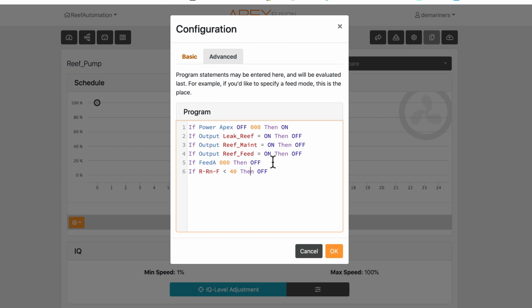You can also, of course, do if my return pump is greater than 100, then turn it off, or greater than 200, then turn it off. You could do anything here with the flow based on the number to turn off and on different things.